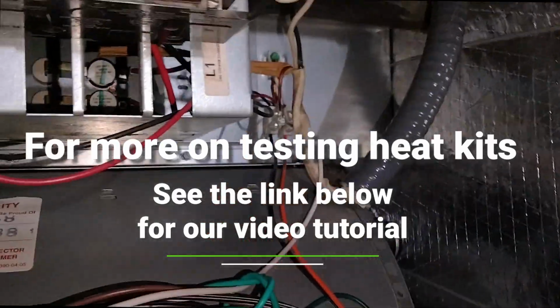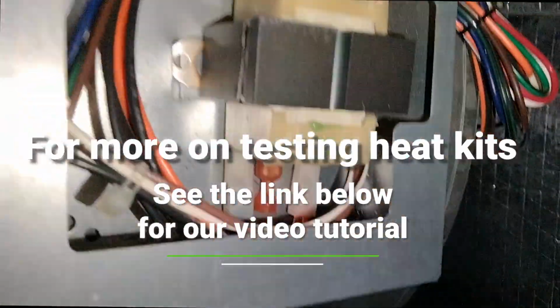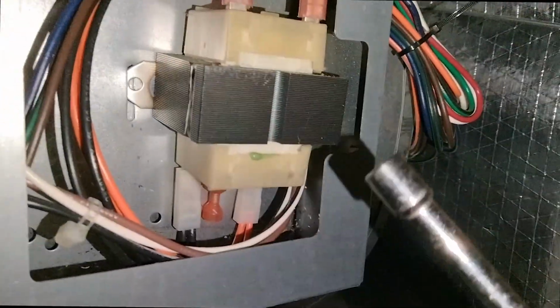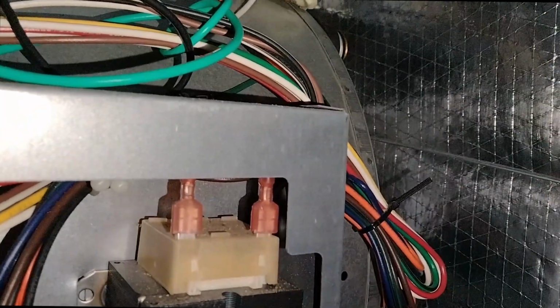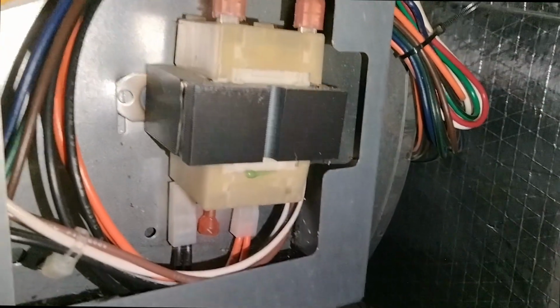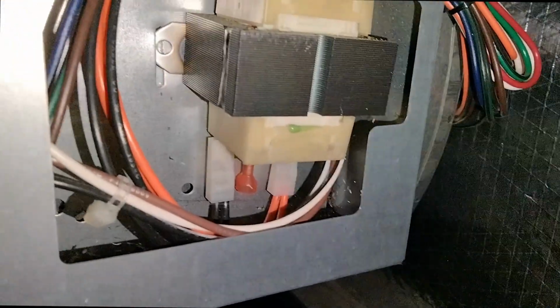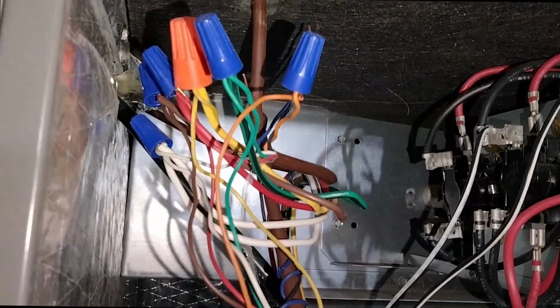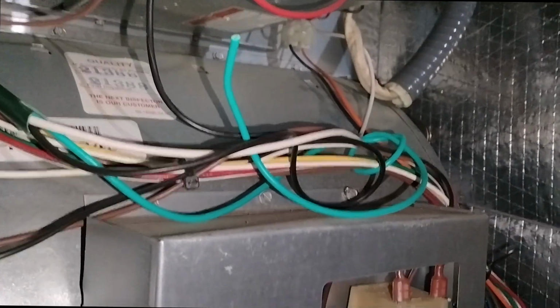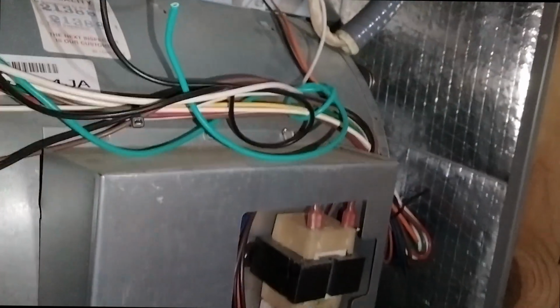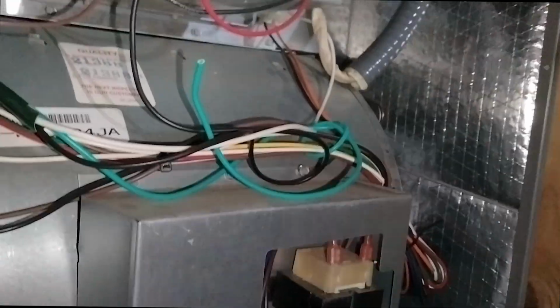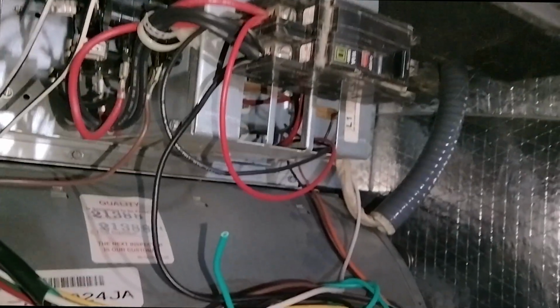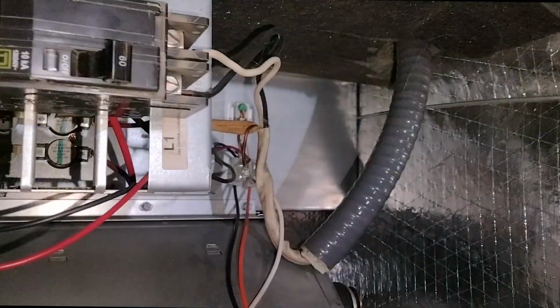and if you are not getting that 24 volts into the unit from your transformer, it's a matter of finding out whether the transformer is bad, whether there's no high side power coming in, or it's not allowing the 24 out, like we said a moment ago, or if you are not getting the call from the thermostat for your heating. So always save yourself a lot of heartache by going through these steps. Always, always, always check power.